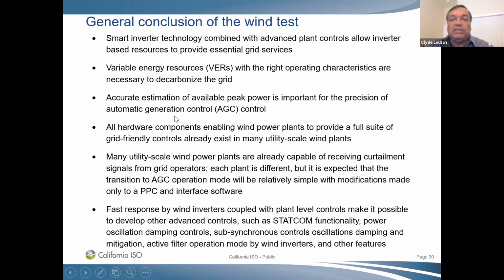This here, I'm not going to go through each one of these bullet points, is really summarizing the findings of that wind test, and it is essentially similar to the solar test. We're not sure yet, but later on this year, the California ISO is going to do a similar test with a 250 megawatt solar battery. In addition to the tests that we did for the wind and solar plants, we can also be looking at things like state of charge and other capabilities that are unique to storage technology, like for instance, the ramp rate at full discharge or close to full discharge and things like that. So we're still working on a test plan, and we're going to be doing that test sometime in the August or September timeframe this year.